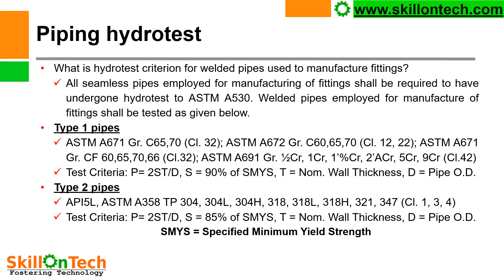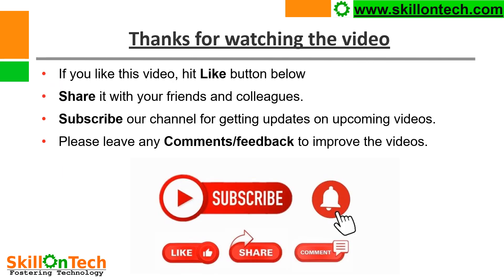Type 2 pipes include: API 5L; ASTM A358 grades TP304, 304L, 304H, 316, 316L, 316H, 321, 347, class 1. Test criteria: P = 2ST/D, where S = 85% of SMYS, T is nominal wall thickness, and D is OD of pipe.